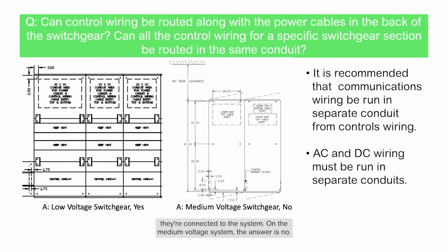On the medium voltage system, the answer is no. The back area where the power cables come into the switchgear is specifically for the power cables. The controls for that medium voltage switchgear would be in the 2x8-inch opening you see in the front portion of that switchgear.